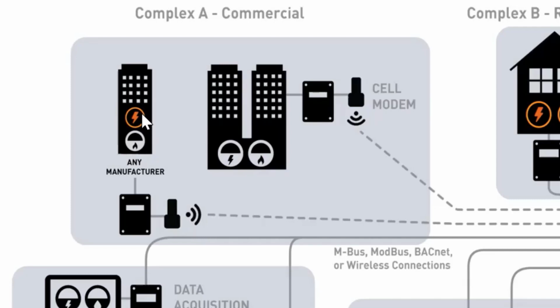New electrical meters would probably need to be installed in quite a few of the properties, whether that's to break out tenant loads or to break out critical electrical loads within the facility. We would aim to install those new meters and connect them to the same data logging equipment that we're getting the existing metering data from.